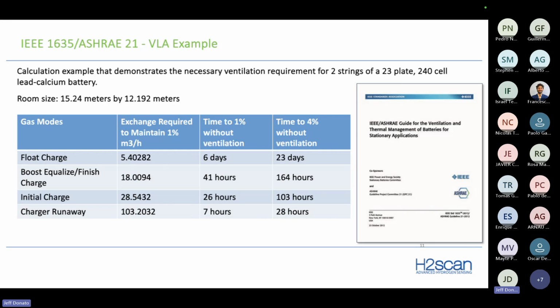So if we remember back at the picture of the ceiling being damaged because of hydrogen accumulation and an ignition of that hydrogen, even though the alarm system was going on for 3 days, obviously the condition was going on for much longer. And because rooms aren't completely sealed, they probably had that ventilation system off for a month or more. So I would say well over 30 days. And then the time to accumulate to 4% without ventilation is 23 days.